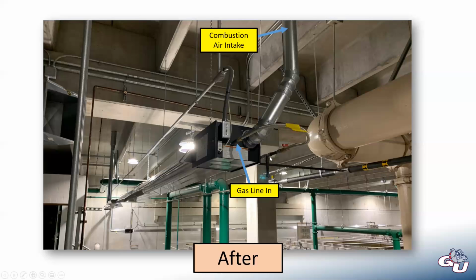This is not actually installed correctly. I can't see one that is in this shot, but I asked them to change it. Basically, you're supposed to force a change in direction of the gas. What should have happened is the gas comes horizontally, then hits a T with the trap on the bottom, then goes up and over to the heater, forcing a change in direction so the dirt falls into the bottom of that trap.